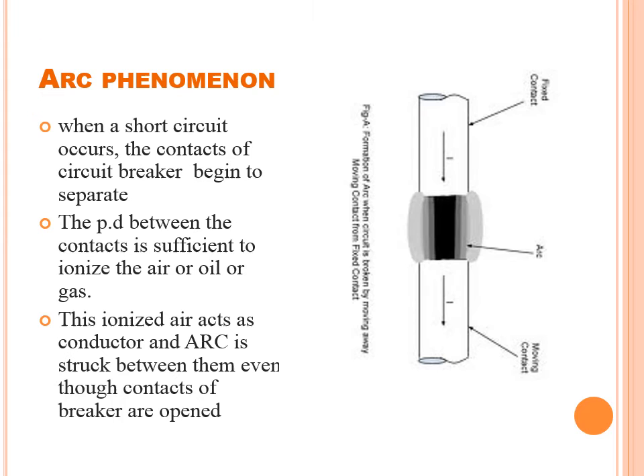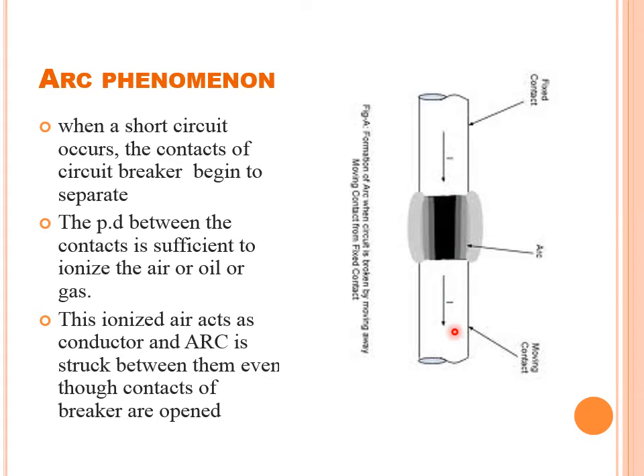Arc occurs in a circuit breaker, which makes it different from simple switches. We will now study how the arc forms, what happens when it forms, and how it can be extinguished. There is a fixed contact and a moving contact. When the moving contact of the circuit breaker gets separated from the fixed contact due to the action of the relay, the contact area between the two contacts decreases and contact resistance causes current density to increase in the fixed contact.